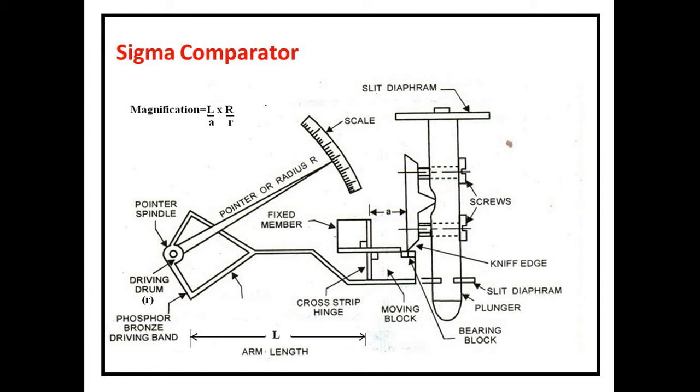You can see here, this is the plunger. Your input signal is going to be here. What is the input signal? It is how the dimension is measured. Suppose you are producing a shaft of, say, diameter 100 mm, and you are producing 1000 such shafts. After the 1000 shafts have been produced, the next task is to measure the dimension, whether it is okay or not okay.